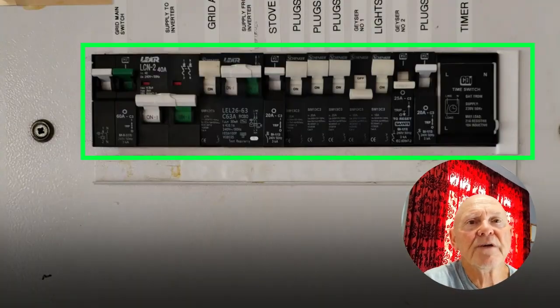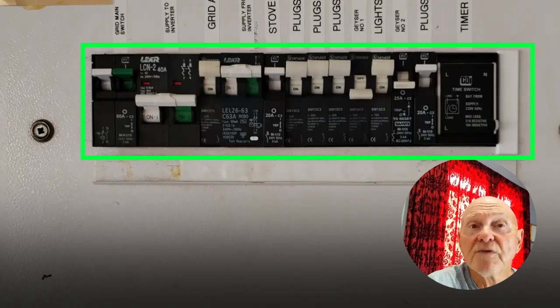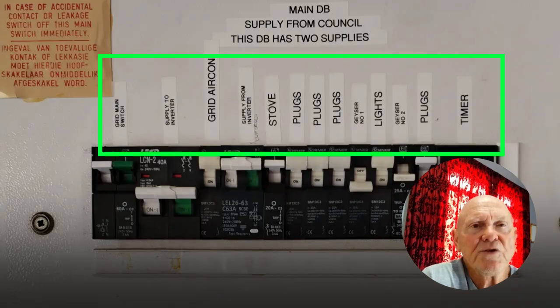A proper DB, distribution board, upgrade often includes time spent on things like sorting out messy wiring so it's not a spaghetti bowl. This means neat and tidy wiring, which will make fault finding in the future easier. Easier means that the electrician spends less time sorting out wires, which means less money from your wallet. Making sure every opening is properly closed, not taped over. Making sure the important safety switch fits properly with no gaps around it. Making sure every circuit is clearly labeled, which enables you to do the correct switching during an emergency, and checking that the switches match what they're protecting. In other words, the plug circuits do not exceed 20 amps, and the light circuits do not exceed 16 amps.